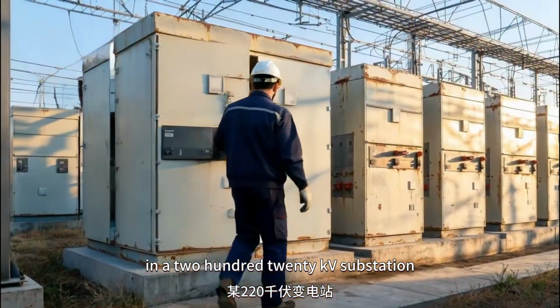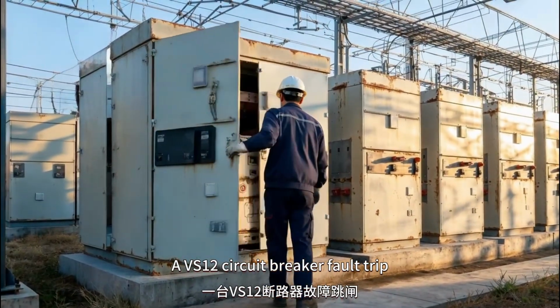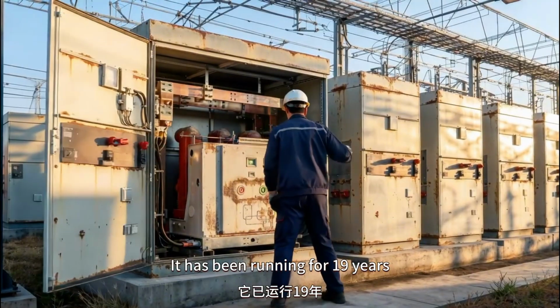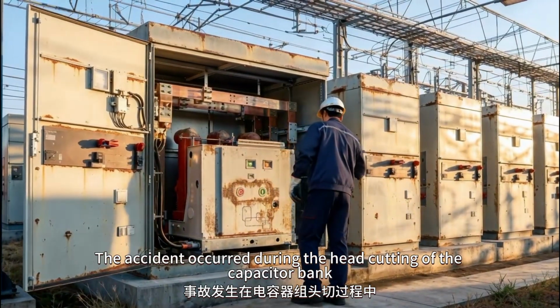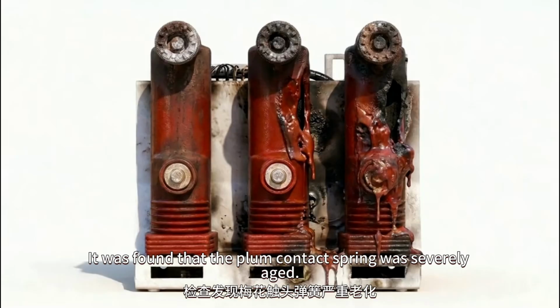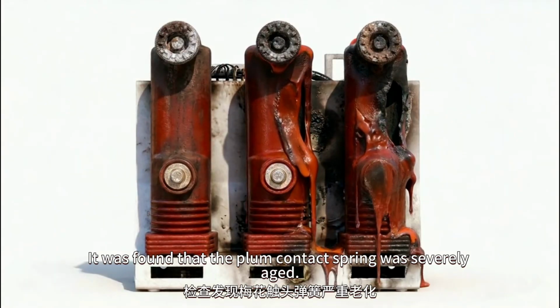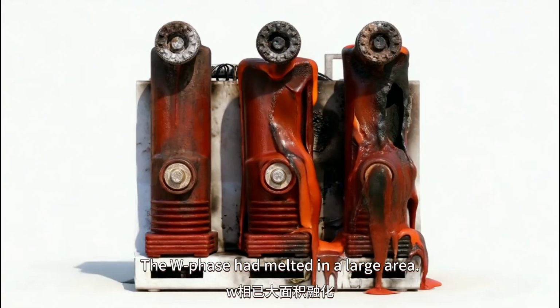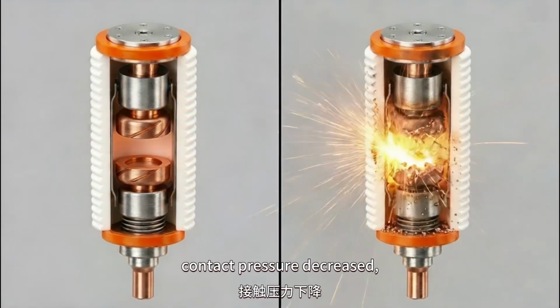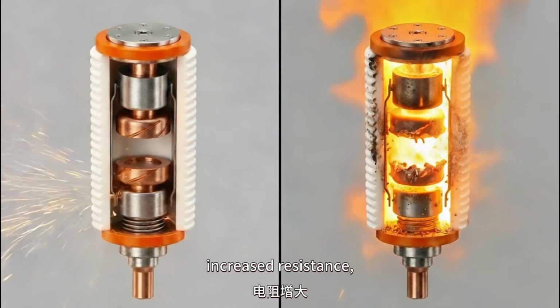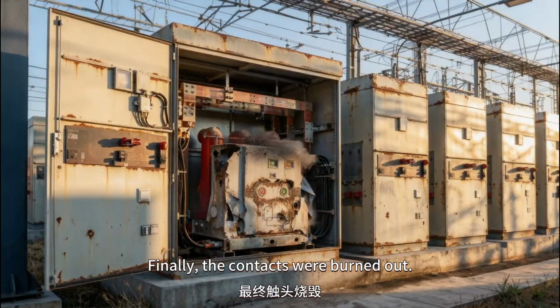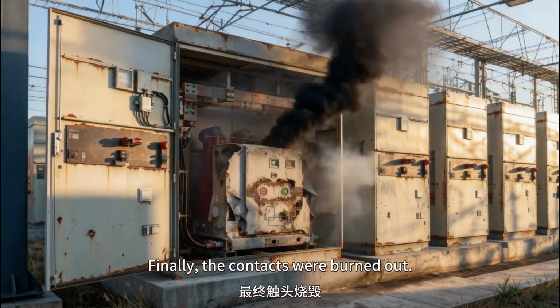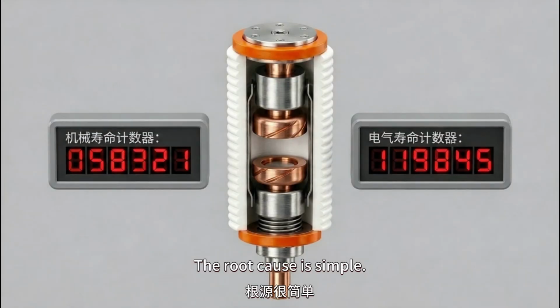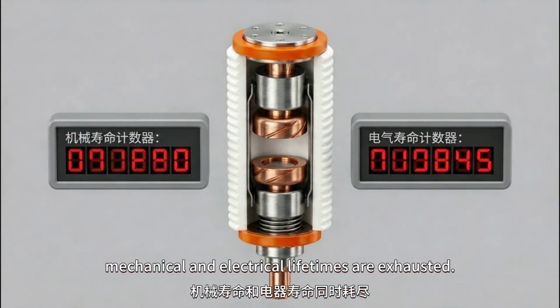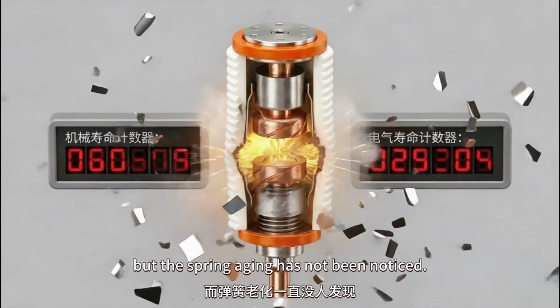In April 2024, in a 220 kV substation, a circuit breaker faulted and tripped. It had been running for 19 years. The accident occurred during the switching of the capacitor bank. It was found that the contact spring was severely aged. The W phase had melted in a large area. After the spring failed, contact pressure decreased, resistance increased, and continuous overheating occurred. Finally, the contacts were burned out. The root cause is simple: the equipment should have been scrapped. Mechanical and electrical lifetimes were nearly exhausted, but the spring aging had not been noticed.